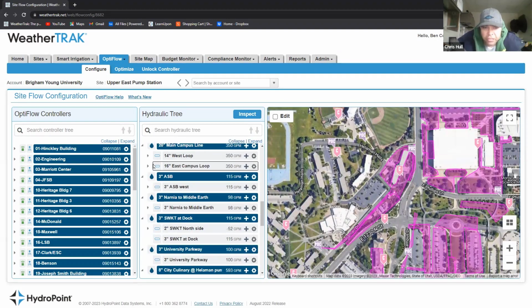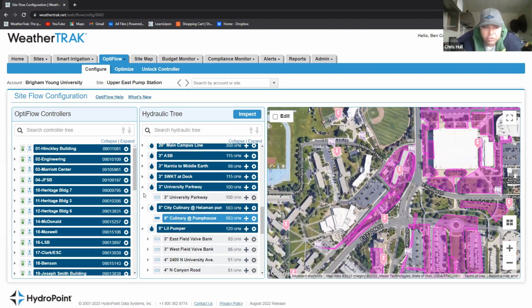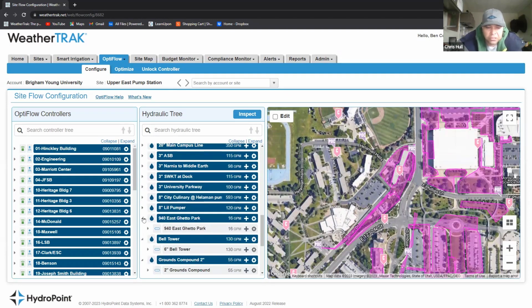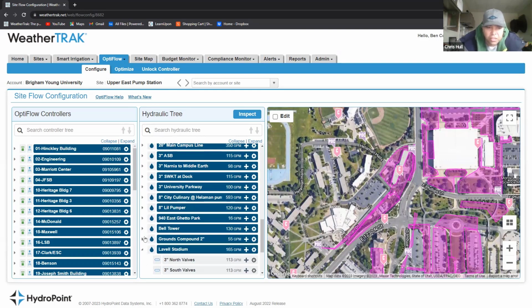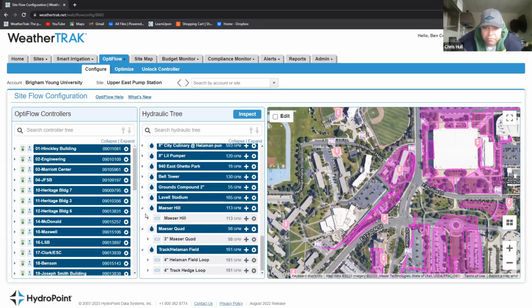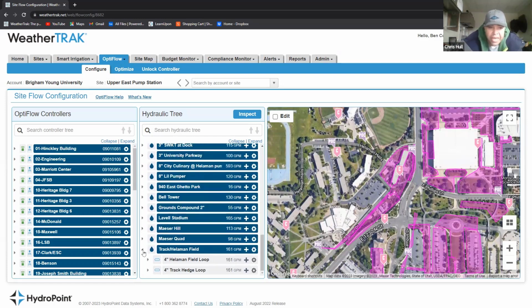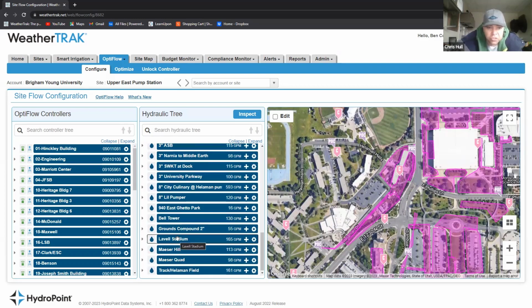But what I've done on that 20-inch main line is try. We used to run like 3 of those pumps at one time, but with access to OptiFlow I can tack that flow down, and I'm trying to run max 2 pumps during the night. So I can maximize that water window, but I can only run those 2 pumps, maximizing those. I have the other 2 pumps in case one goes down. But I can use that to really maximize the pump efficiency and the flow that I'm putting out there.